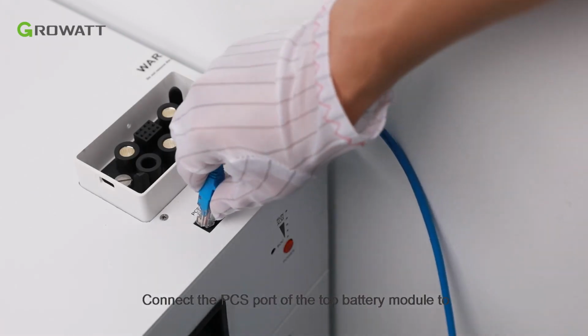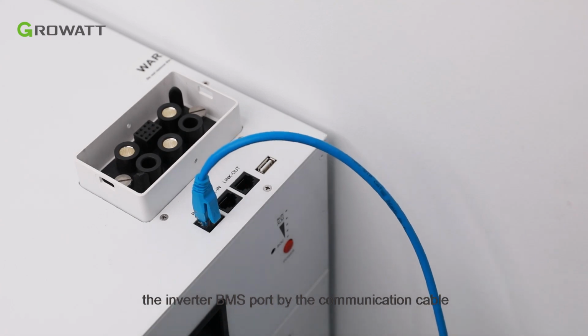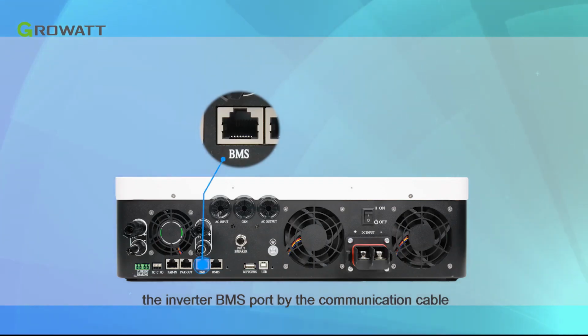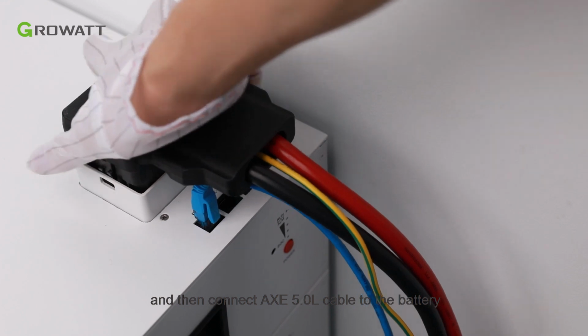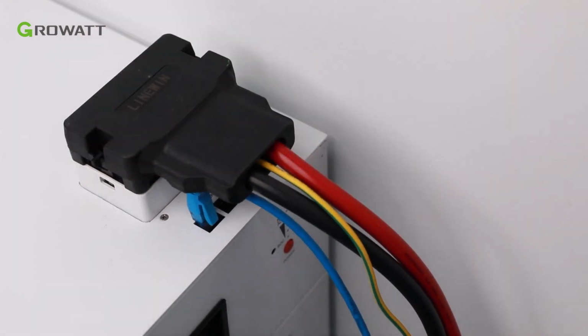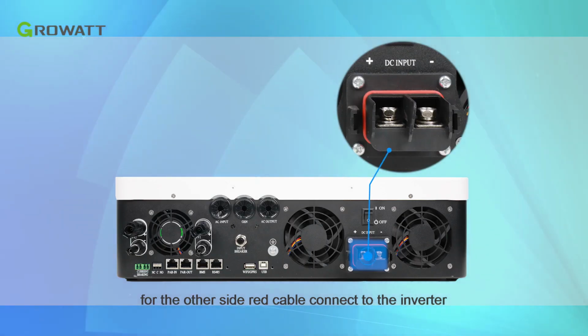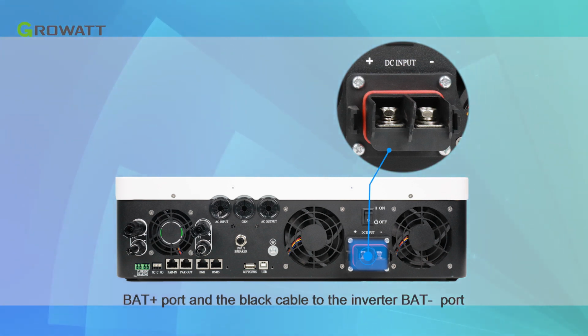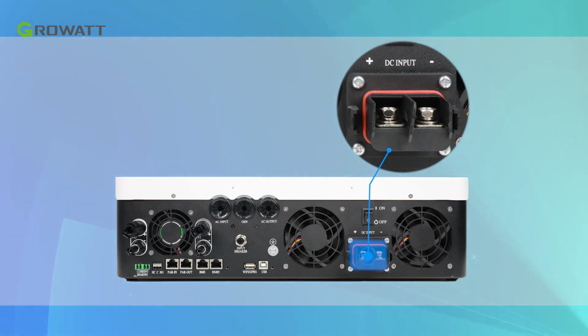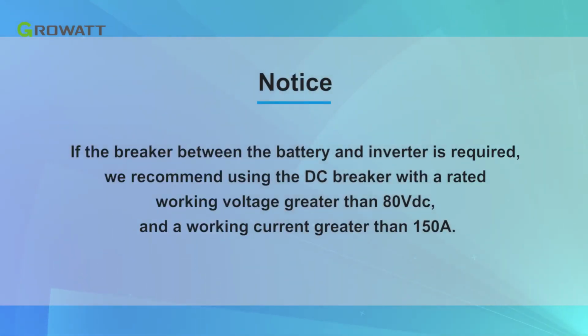Connect the PCS port of the top battery module to the inverter BMS port with the communication cable, and then connect the AXE 5.0L cable to the battery. On the other side, connect the red cable to the inverter BAT positive port and the black cable to the inverter BAT negative port. Notice, if a breaker between the battery and inverter is required, we recommend using a DC breaker with a rated working voltage greater than 80 VDC and working current greater than 150 amperes.